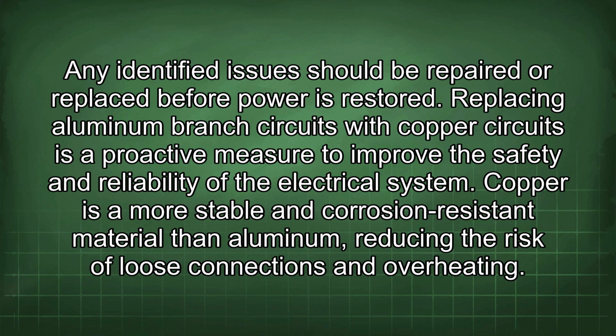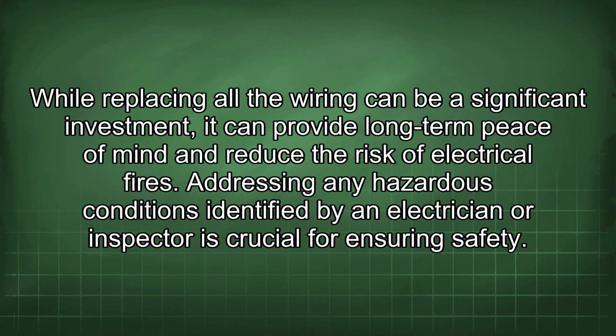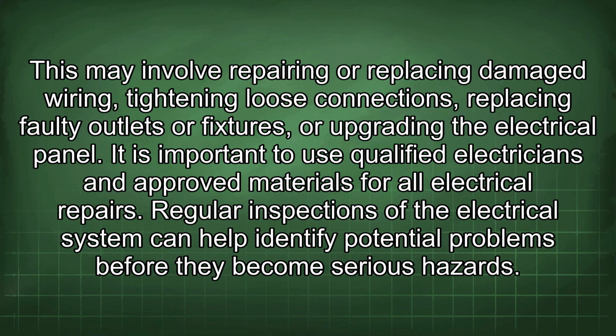Replacing aluminum branch circuits with copper circuits is a proactive measure to improve the safety and reliability of the electrical system. Copper is a more stable and corrosion-resistant material than aluminum, reducing the risk of loose connections and overheating. While replacing all the wiring can be a significant investment, it can provide long-term peace of mind and reduce the risk of electrical fires. Addressing any hazardous conditions identified by an electrician or inspector is crucial for ensuring safety. This may involve repairing or replacing damaged wiring, tightening loose connections, replacing faulty outlets or fixtures, or upgrading the electrical panel. It is important to use qualified electricians and approved materials for all electrical repairs.